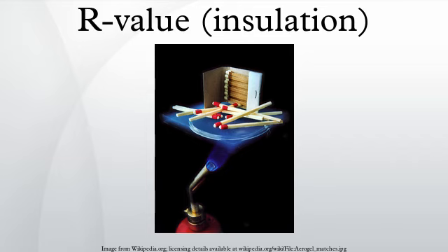Factors. There are many factors that come into play when using R-values to compute heat loss for a particular wall. Manufacturer R-values apply only to properly installed insulation. Squashing 2 layers of batting into the thickness intended for one layer will increase but not double the R-value. Another important factor is that studs and windows provide a parallel heat conduction path that is unaffected by the insulation's R-value. The practical implication is that one could double the R-value of insulation installed between framing members and realize substantially less than a 50% reduction in heat loss.